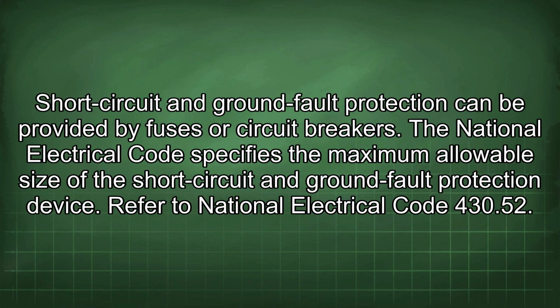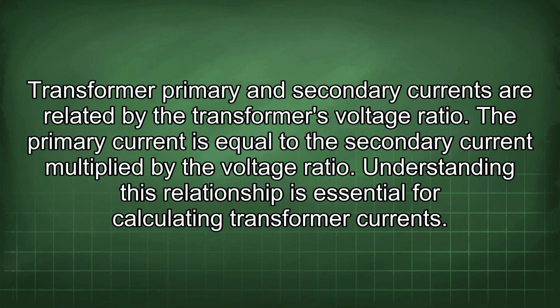Short circuit and ground fault protection can be provided by fuses or circuit breakers. The National Electrical Code specifies the maximum allowable size of the short circuit and ground fault protection device. Refer to National Electrical Code 430.52. Transformer primary and secondary currents are related by the transformer's voltage ratio.